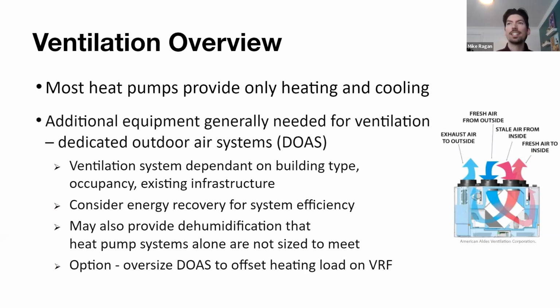Sometimes we're able to have direct ducting straight to our equipment with an in-duct heater directly from outside, and that's all the ventilation we would need. Other times we'll utilize a whole ventilation system that has ductwork laid throughout the building that delivers air separately to a space, or integrates with the VRF equipment to deliver a mix of fresh and recirculated air to the space. With that, we want to consider energy recovery in order to heighten system efficiency. That would be utilizing the waste heat that we're exhausting from the building to preheat the incoming air from the outside, so that the DOAS system isn't going to have to pick it up from 10 degrees to 70. It would only need to go from 10 degrees to 40, and the rest of the delivered neutral air would come through an energy recovery system.